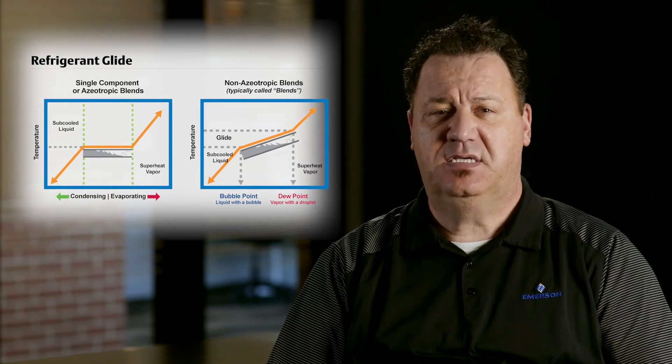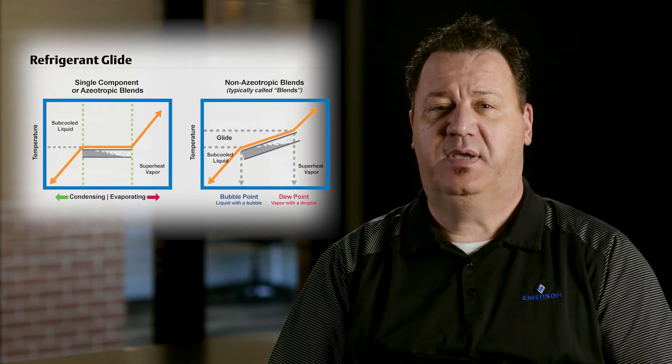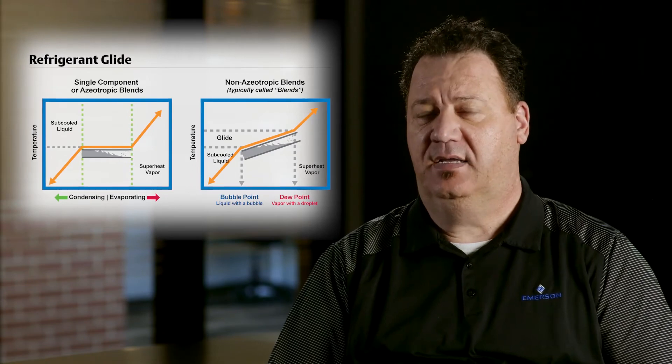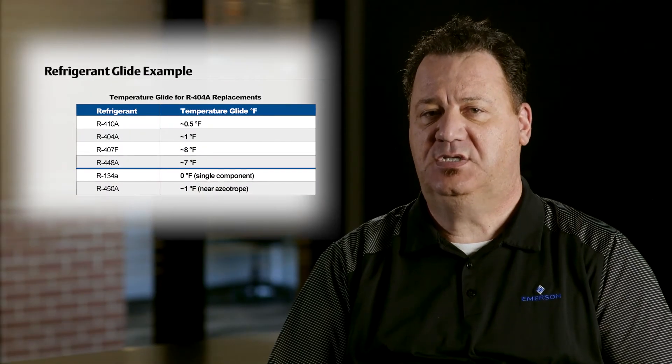An azeotropic blend has minimal Glide. A good example for that would be R410A — it has less than half a degree of Glide, which is non-significant.